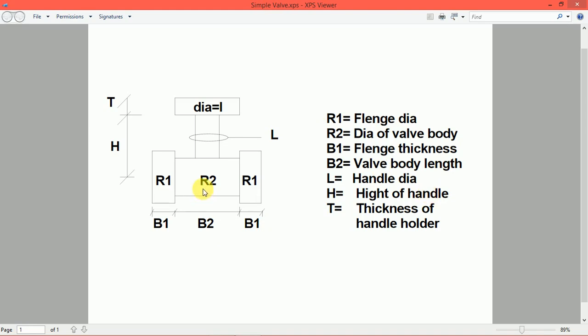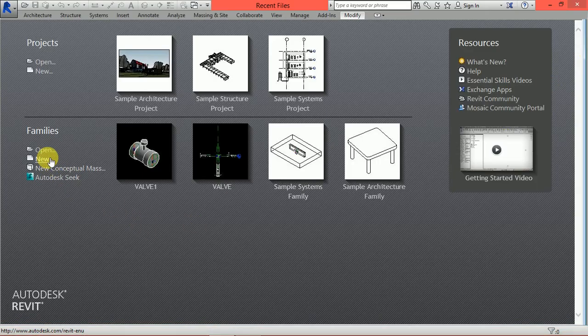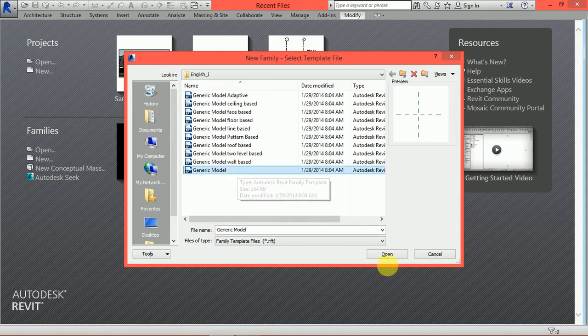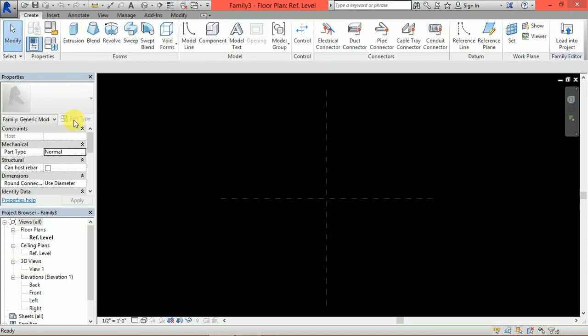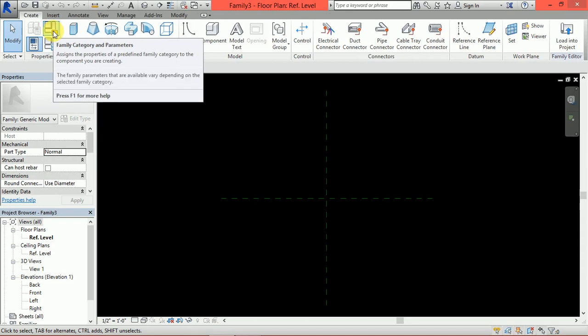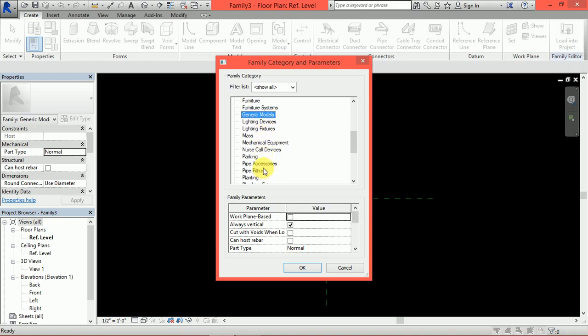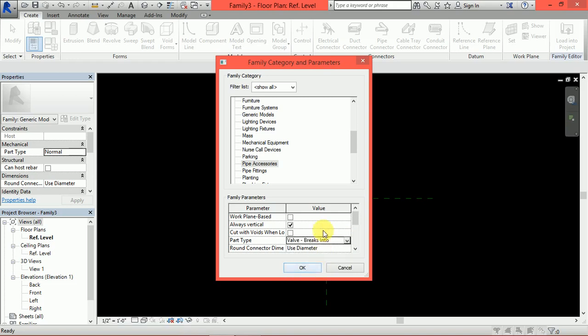Now, I will go Revit Session. I will click New Family, Generic Model, Family Template and Open. Now, I will go to Family Category and Parameter. I am creating a valve. Valve is a pipe accessory. So, I will create here pipe accessories. I will click on valve break into because I place valve in the pipe by breaking.